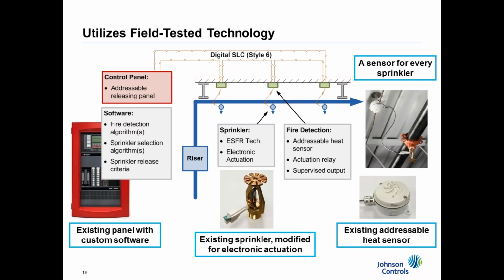So to break down some of the parts, the way this application works is we're using an ESFR technology. The ESFR technology we selected was our ESFR K17 pendant sprinkler. That gave us, for this first application, the best use of water and pressures in facilities, especially existing facilities that need to upgrade their systems, maybe because a class commodity has changed. In the 80s, there were a lot of K14s put in for a class 3 commodity, but the fire officials are now coming in saying, okay, you're storing unexpanded or expanded plastics, and your sprinkler system is not up to the capabilities of protecting that. So we chose that ESFR technology because in those types of facilities, you were dealing with a 3/4 inch thread where your sprinkler went into your pipe, and this same thread will work.